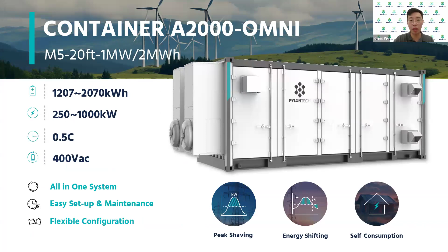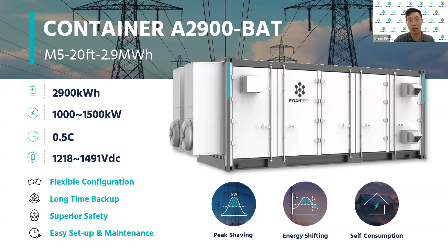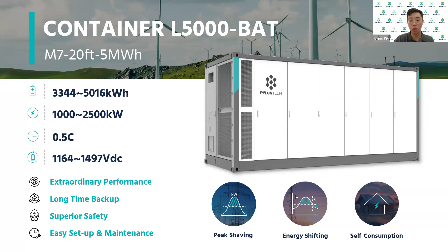For this one, it's also a 20-feet container, but without the PCS inside. For this kind of solution, we have 2.9 megawatt hour inside the container. And the customer can choose the outdoor size of the PCS. Usually we use an outdoor PCS like 1.5 megawatt power to combine with this kind of solution. And this is currently the largest size we have. It's a liquid cooling 20-feet container, and it can provide 5 megawatt hour capacity. For this size, it's usually for long-term backup, or for grid service with this large system.